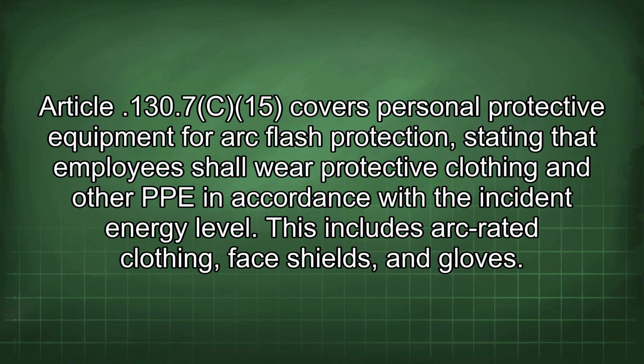Article 130.7(C)(15) covers personal protective equipment for arc flash protection, stating that employees shall wear protective clothing and other PPE in accordance with the incident energy level. This includes arc-rated clothing, face shields, and gloves.